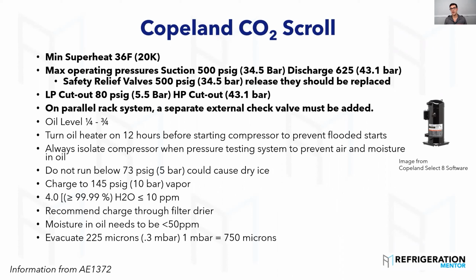Maximum operating pressure on the ZO scrolls is 500 PSI. This is standstill pressure. Discharge 625. There's a mandatory safety relief of 500 PSI. This is UL rated for North America. It always needs to be open to the system. So you have to have a valve on there where you close it and it always has that port open. So it's a two-way valve. One port's always open, and that's where the safety relief needs to be connected, or it always needs to be open to the system either way on that suction line.